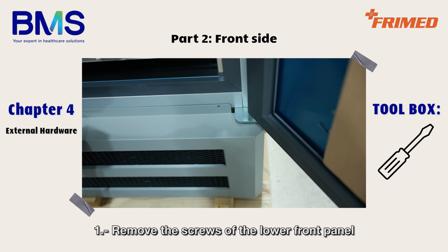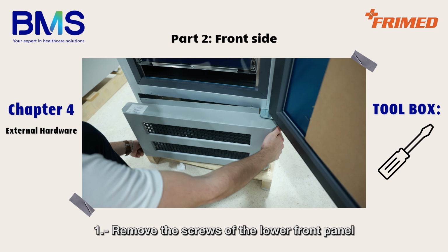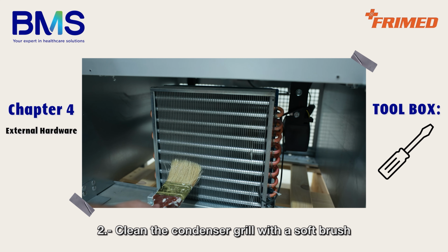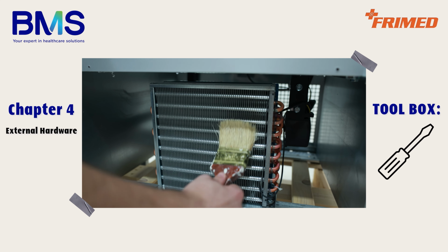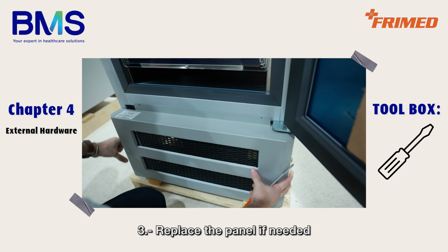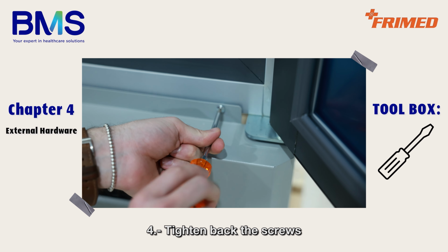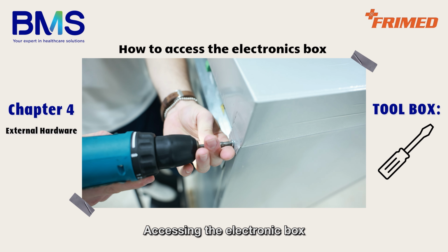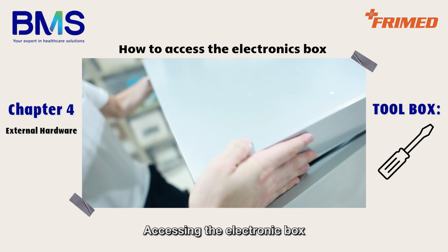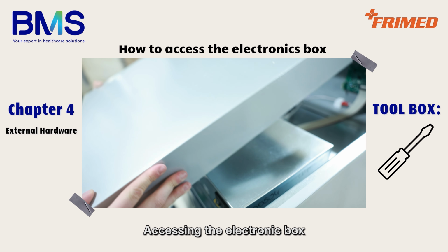Part 2. Front side. Remove the screws of the lower front panel. Clean the condenser grill with a soft brush. Replace the panel if needed. Tighten back the screws. To have access to the electronics box, just remove the screws from the top rear of the unit and remove the upper panel.